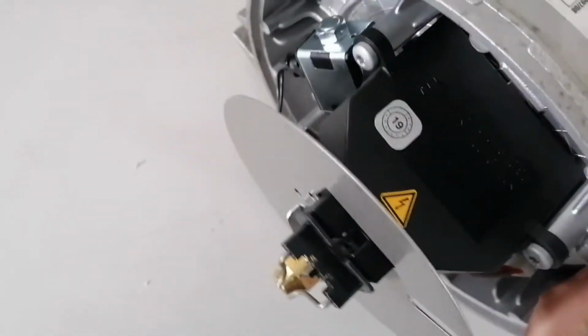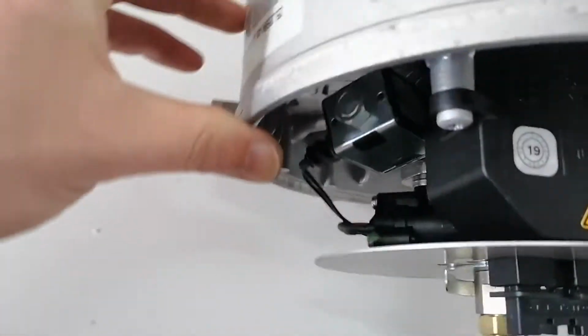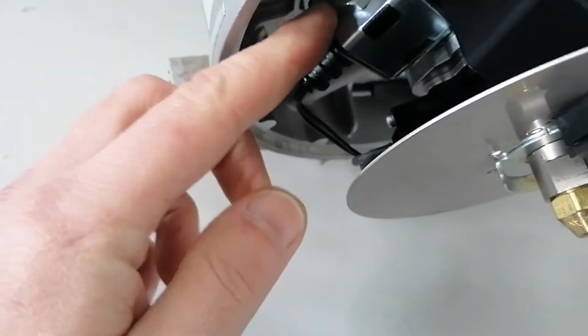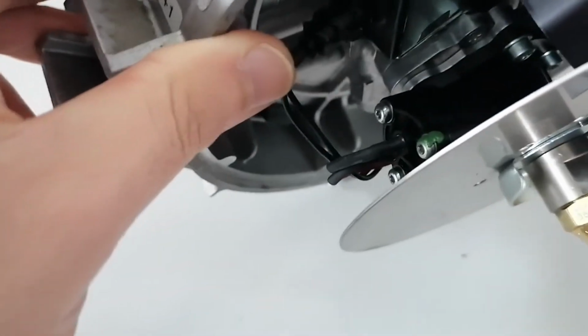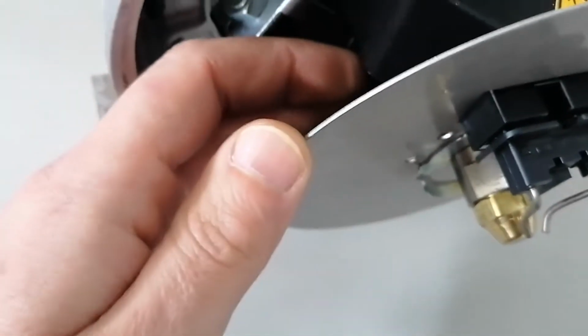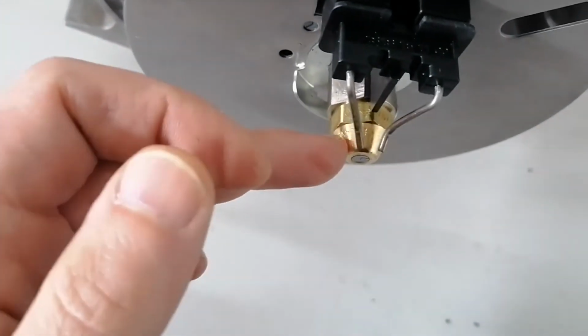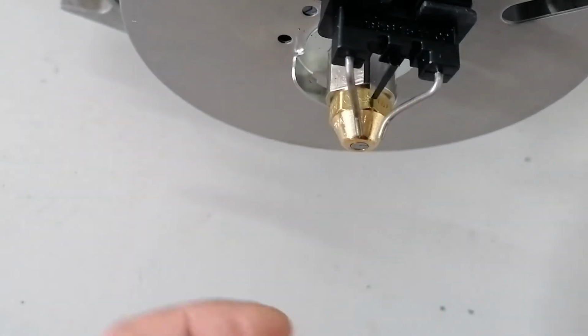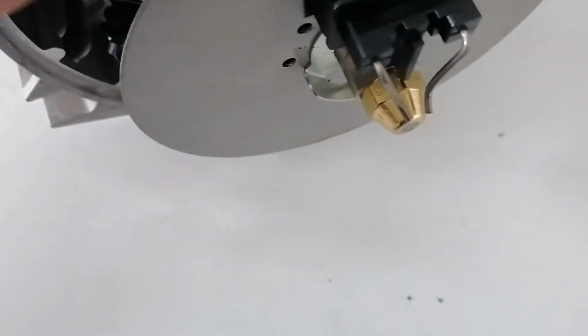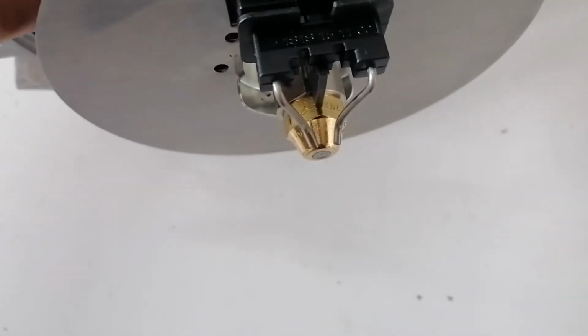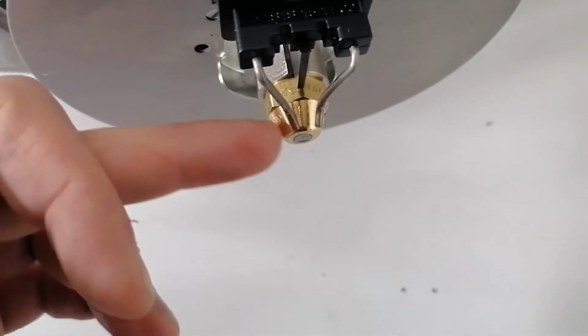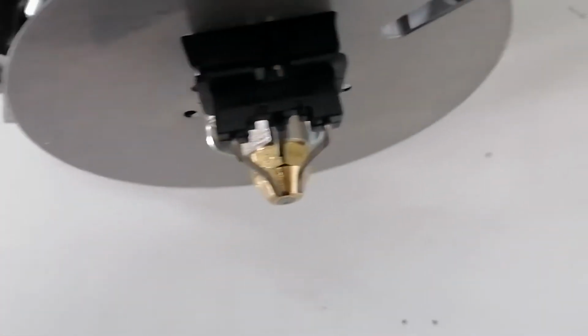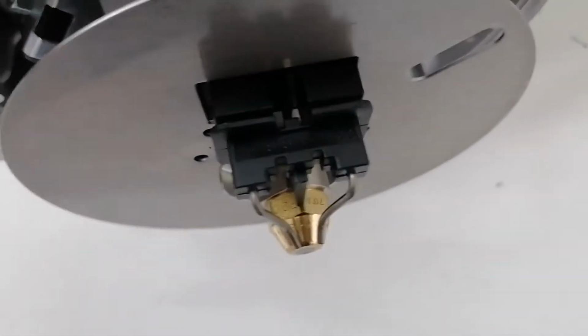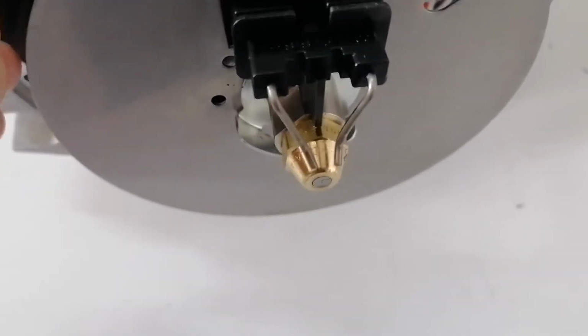So when the unit is turning on, we have right here a little solenoid valve that opens the fuel. Then part of the fuel, with I think 10 bars of pressure, comes through the nozzle and gets sprayed, and the rest of the fuel, which doesn't come out here, goes back on the return line to the fuel tank.